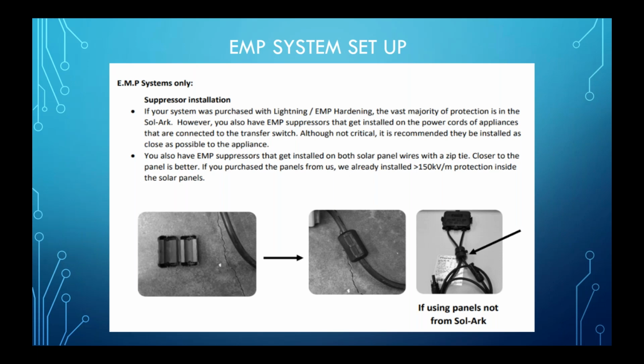And then we recommend putting a zip tie around that. A little bit of military redundancy there, but it is an outdoor application. So, thermal expansion, hot, cold, hot, cold, hot, cold. We do recommend putting a zip tie on that. So again, you get 20 of the suppressors for the appliances in the home, 40 of the suppressors for the panels, and that's how they both get used.